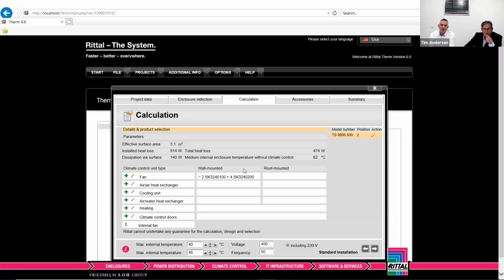So without going on about that too much, let's get back to these fans. I was able to pick these two fans based on a heat load of 474 watts, okay? Now I've got other options here. I could actually use a cooling unit, but in this case I wouldn't, because dust really isn't a problem. I don't have a high IP rating to worry about, and my equipment can sit up to 45 degrees without hurting itself.